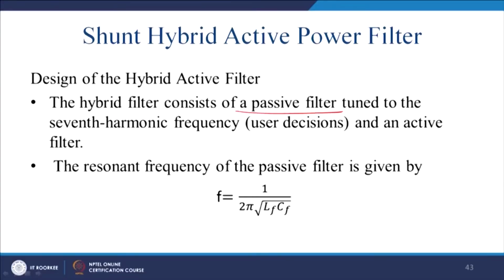And let us now talk about the design of the passive part of this hybrid filter. The hybrid filter consists of the passive filter tuned to the 7th harmonic. Look, I have shown in the block diagram that the 5th harmonic has been extracted and put like that, and thus the main chunk left out was the 7th harmonic. So, for this reason the passive filter has been designed for the 7th harmonic, and this has been found to be optimal. Because of lack of time I cannot go into this study, and I have personally done the study.